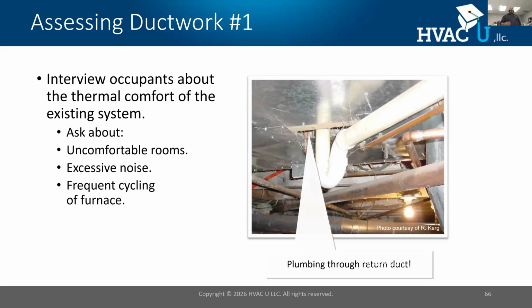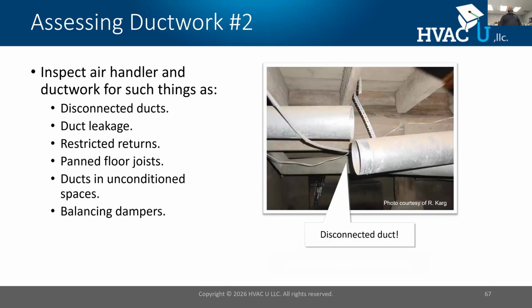And then do a physical inspection. We see here that a plumber was kind enough to cut some plumbing work to a return. That was nice of them. In this situation, we call this bootleg ducting. Sometimes it's good old fashioned evaluation of the duct system to see what's going on. Oftentimes, the problems are pretty apparent. So remember, look for things like this, but you also want to determine with your tests what are the things you can identify with those duct systems.